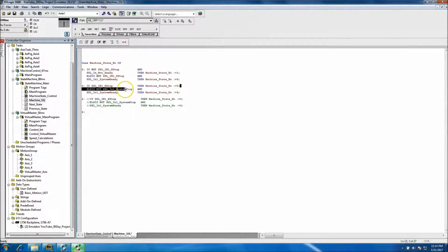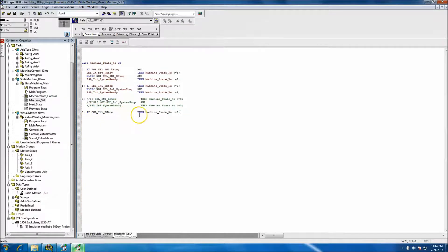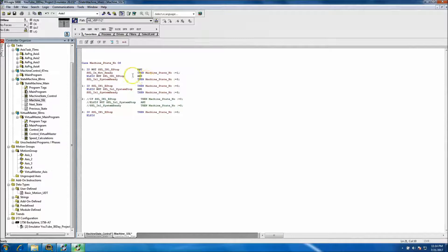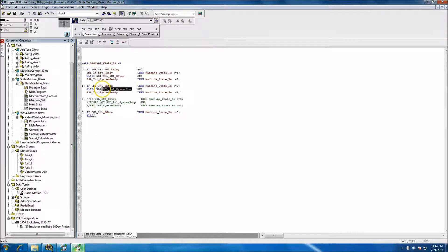State 3 is going to start the same way: if no e-stop, we'll just copy and paste that. Then we'll come back and say ELSE IF. The ELSE IF will basically be looking at the stop — so if a stop happens or if not ready happens, we want to index to State 1. So if a machine stop happens...